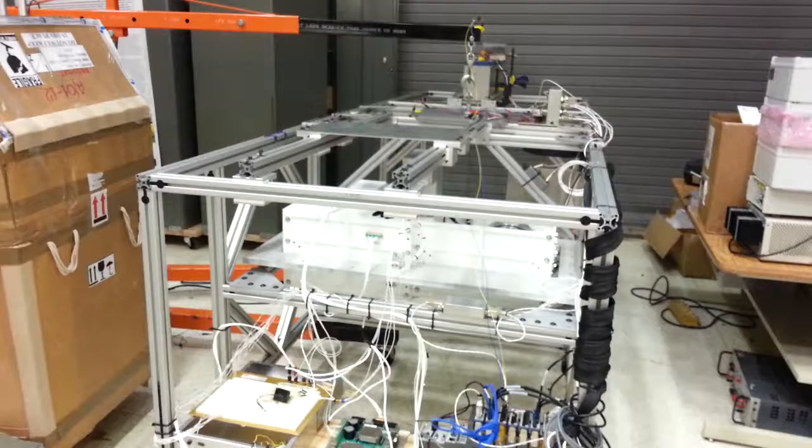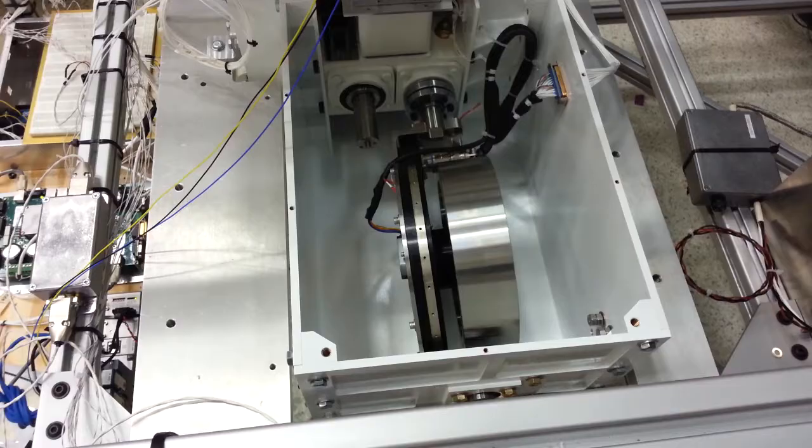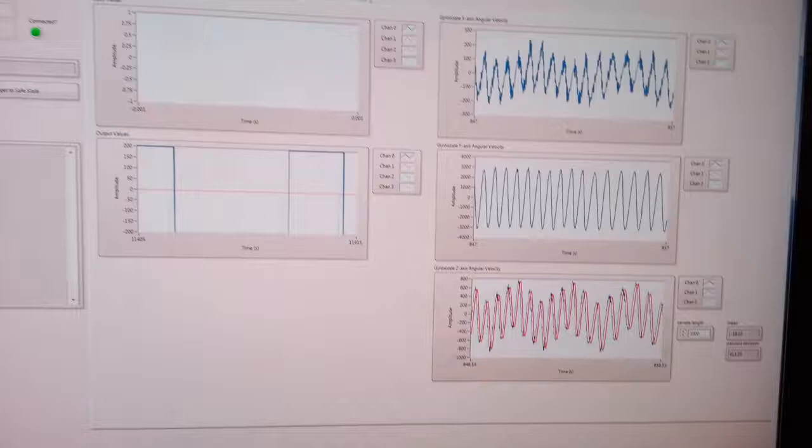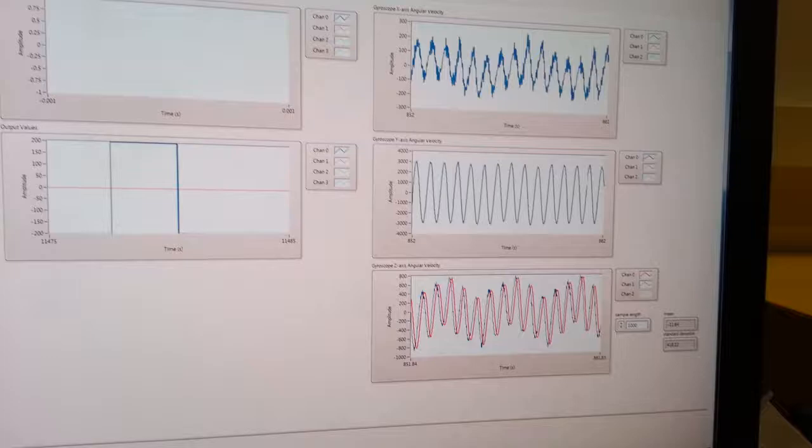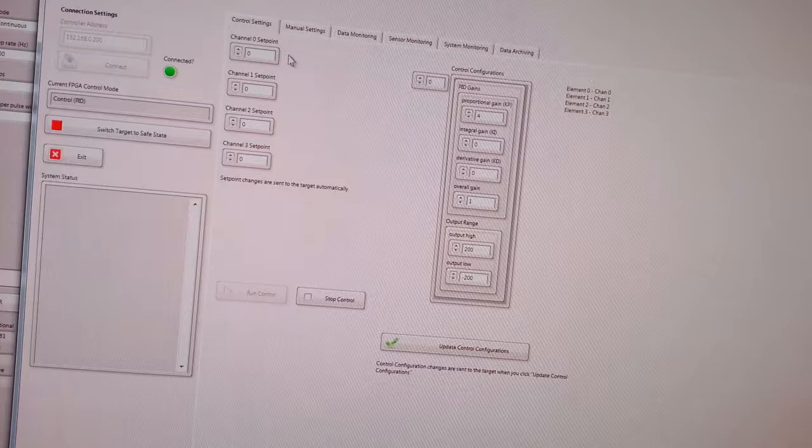Pretty consistent beat here. So the problem is that the PID gains are too high and the output is saturating.